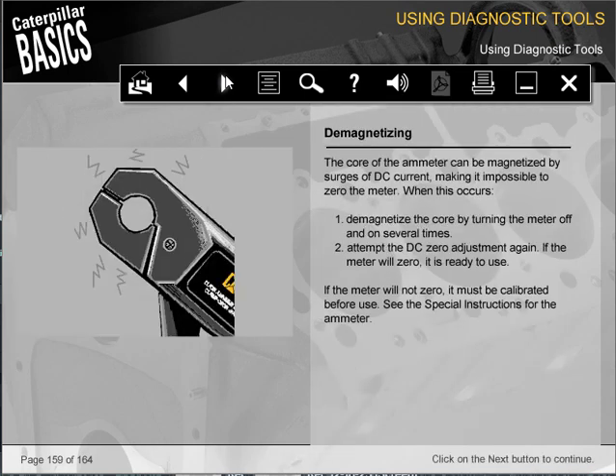The core of the ammeter can be magnetized by surges of DC current, making it impossible to zero the meter. When this occurs, 1. Demagnetize the core by turning the meter off and on several times. 2. Attempt the DC zero adjustment again. If the meter will zero, it is ready to use. If the meter will not zero, it must be calibrated before use. See the special instructions for the ammeter.